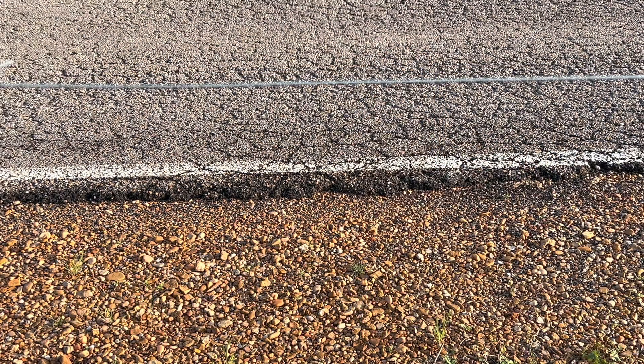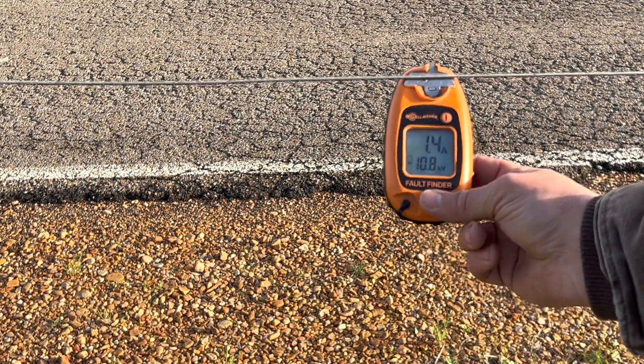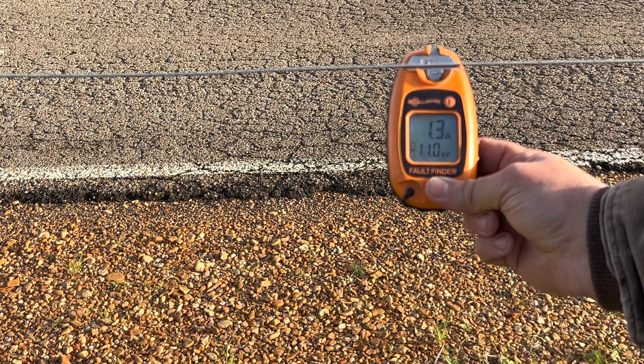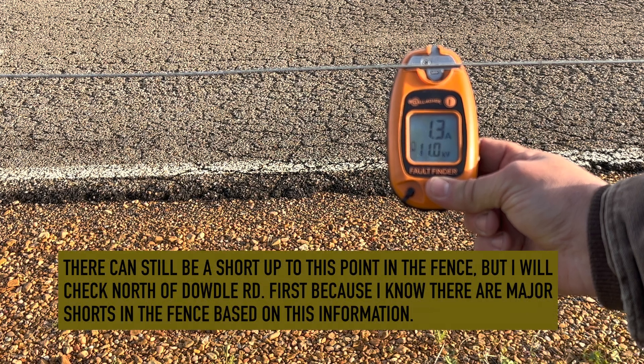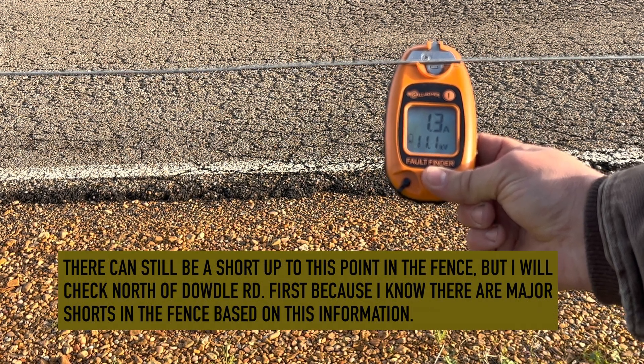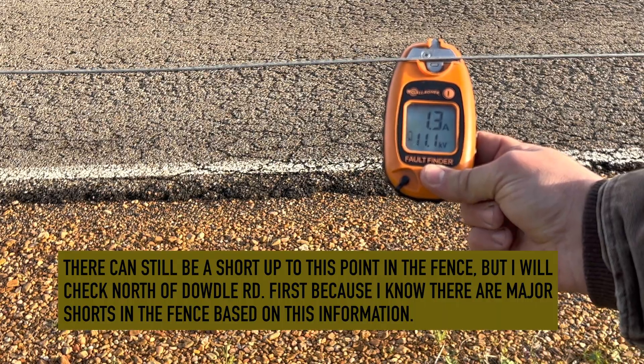Now that I've got the power off north of Dowdle Rd., it's showing 10.9 to 11 kilovolts — an 11,000 volt charge. So I know without a shadow of a doubt that the dominant voltage drop is north of Dowdle Rd..